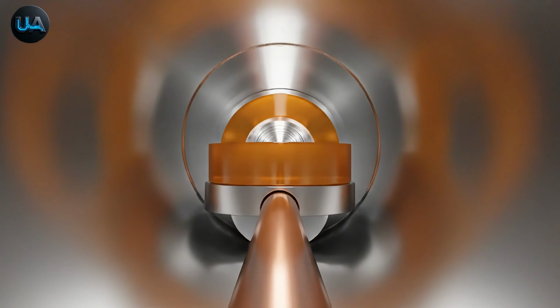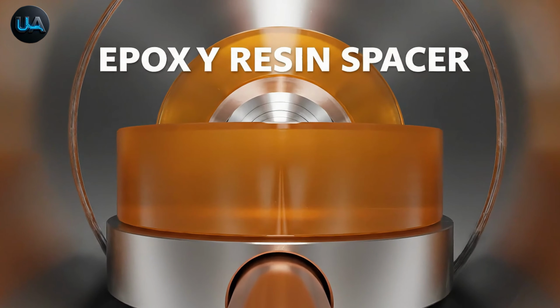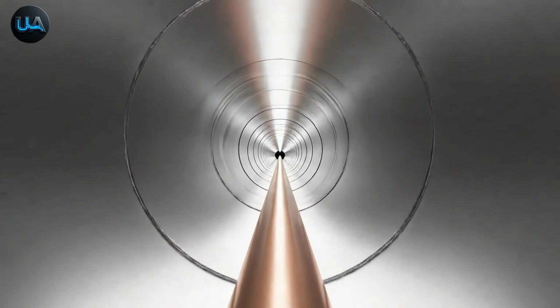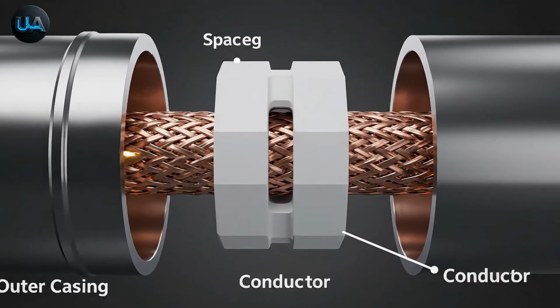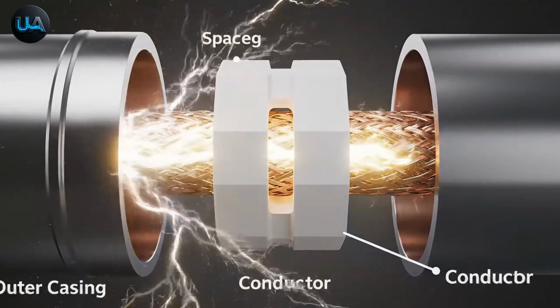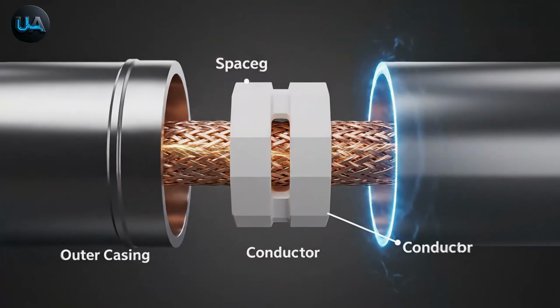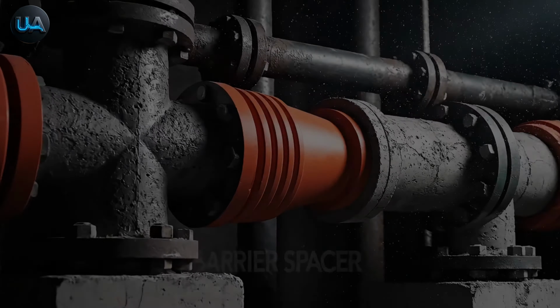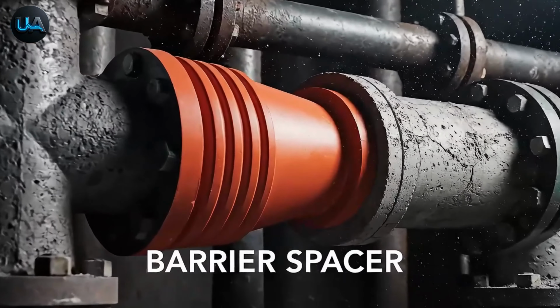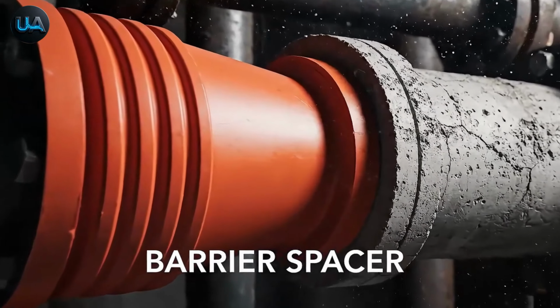To hold this conductor in the middle of the pipe, epoxy resin spacers are used. The spacer mechanically holds the conductor and electrically isolates it from the pipe, preventing short-circuiting with the outer casing. Another type of spacer is the barrier spacer. It completely seals off a chamber.